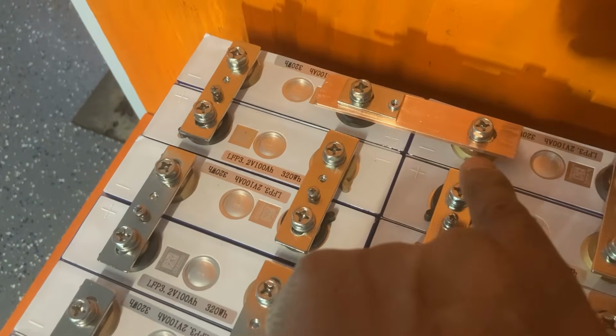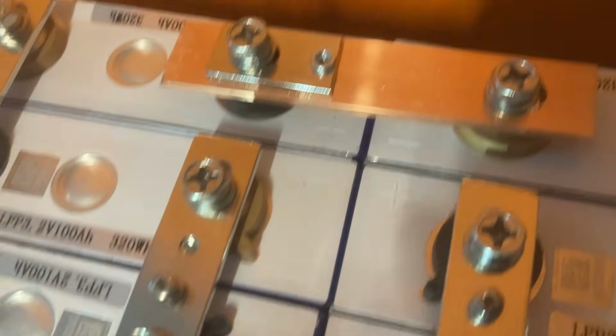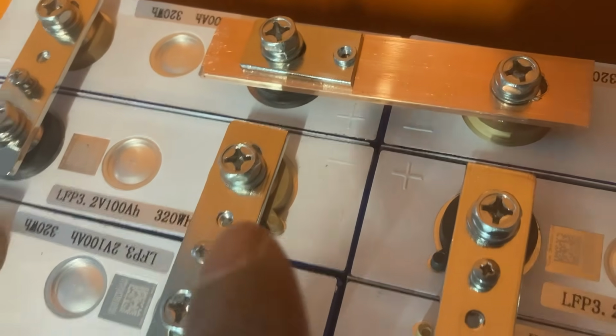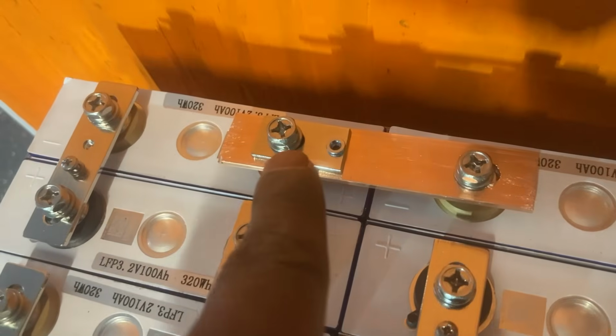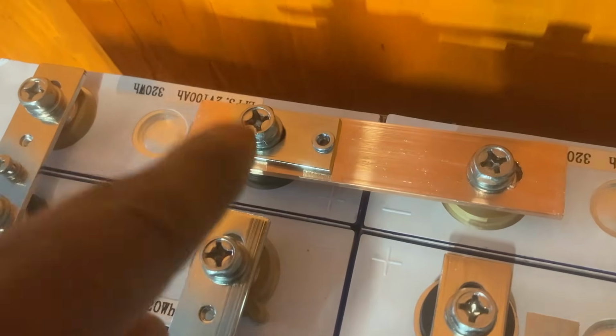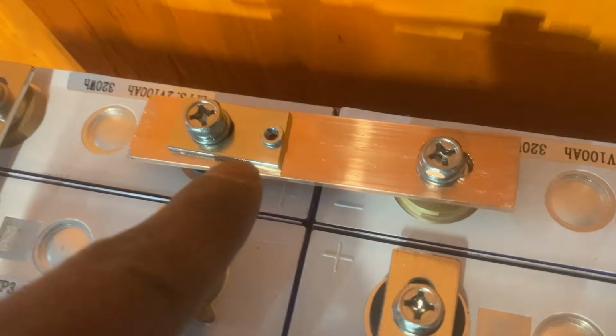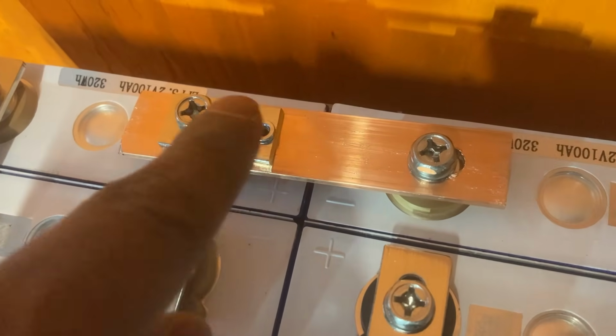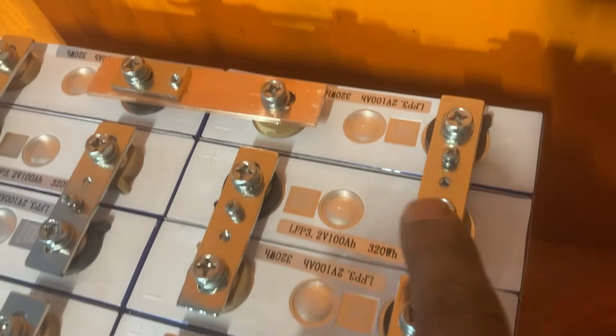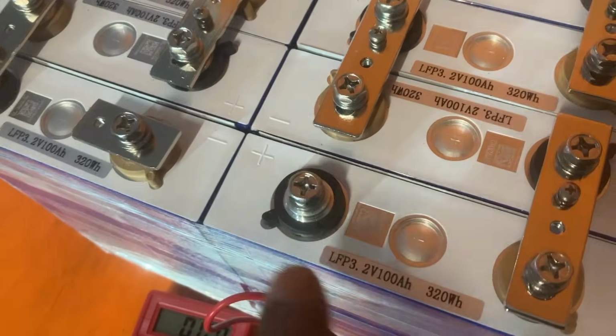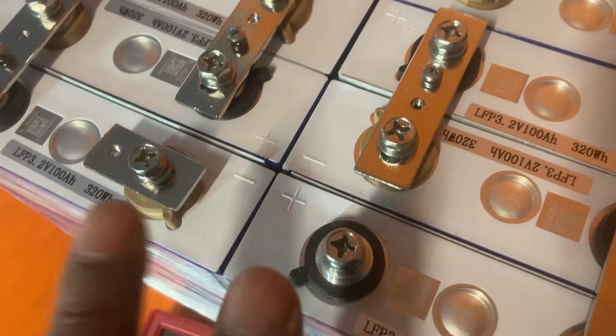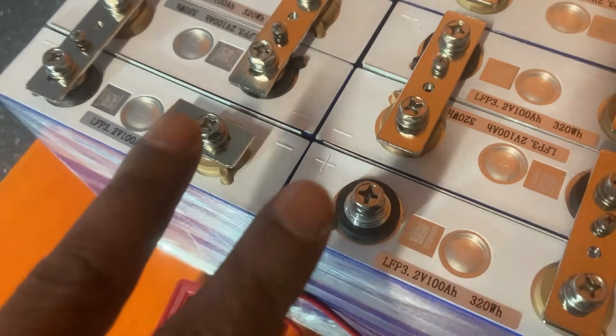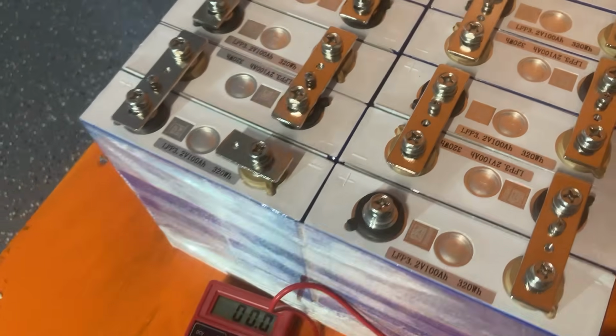To jumper over here, I couldn't use the same bus bars that came with it, so I had to make my own little copper bus bar. I might need a slightly longer screw, but that tightened down there, and I cut the bus bar in half so I could screw in the terminal over there. This makes it 24, and then it continues the circuit over and comes back the other way to this terminal. So I'll have an empty negative and an empty positive, and together these are going to make 48 volts.